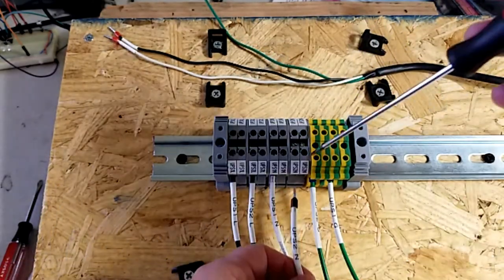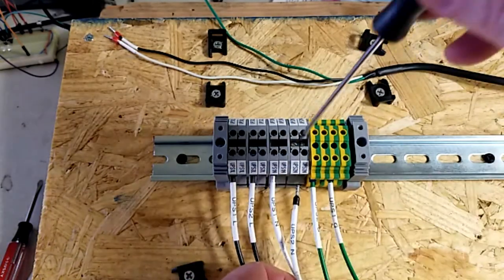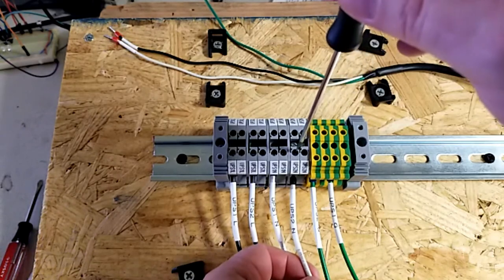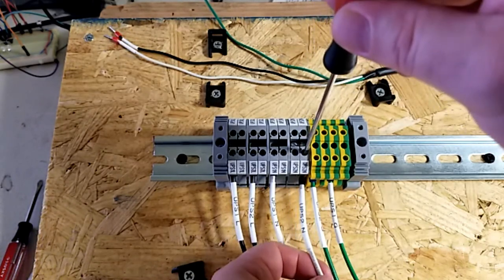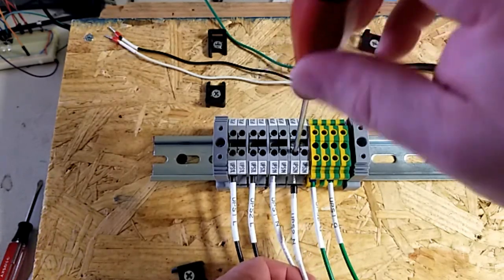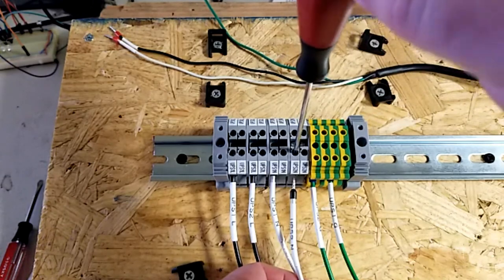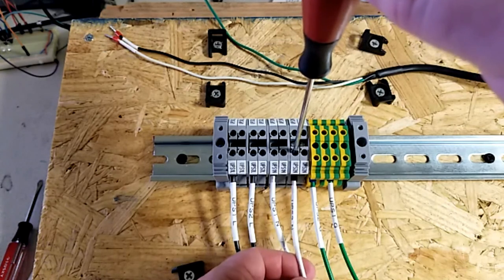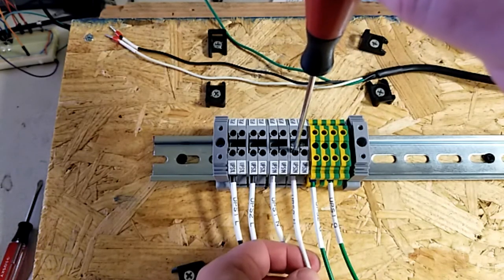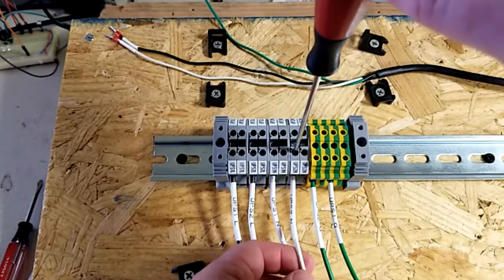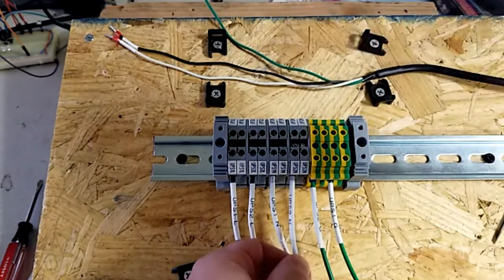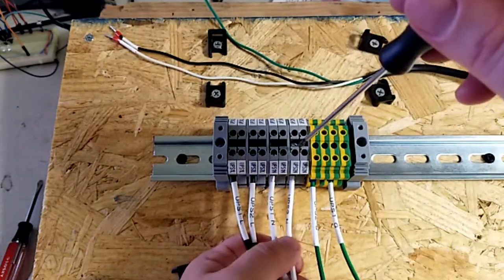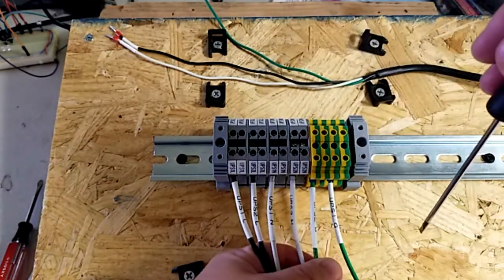We're going to also replace the neutral wire, which is your white wire, that came into the bottom of your neutral terminals. And it does not matter if you go into this first or the second terminal. They're both electrically tied together. They're the same thing. So again, we might loosen this up a little bit. Make sure our wire slides in firmly. You'll see sometimes it catches a little bit when it goes in, but it should go firmly in. The ferrule should go all the way in here. Tighten it down, and again, give it a little tug test. The key is to make sure that all your wires are fully seated as deep as they can go, and then they're cranked down good and tight.